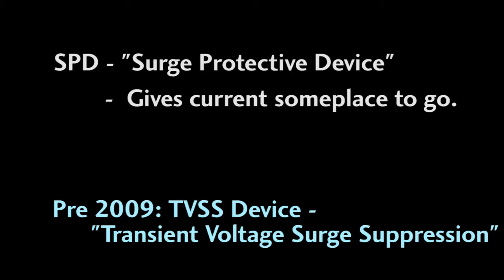SPDs simply give the current someplace to go while the magnetic field around the coil dissipates when you open the circuit. That way it can't build up that huge voltage spike.